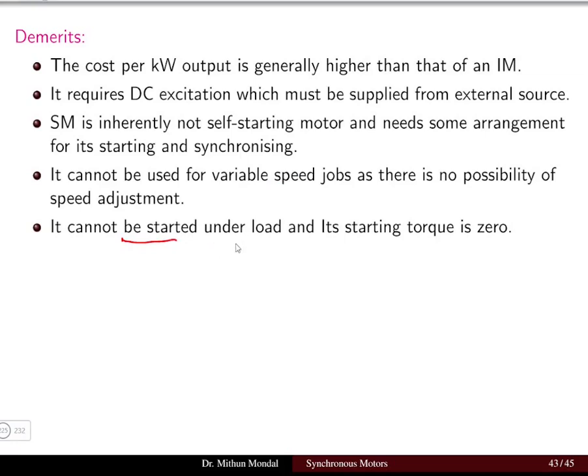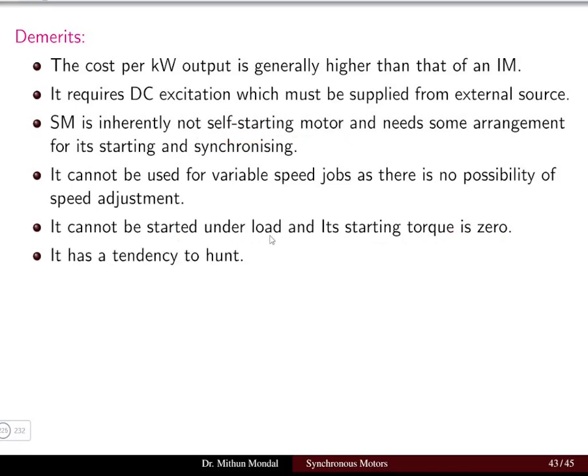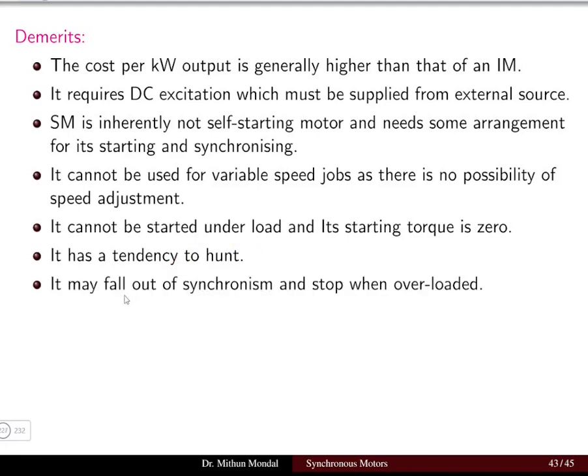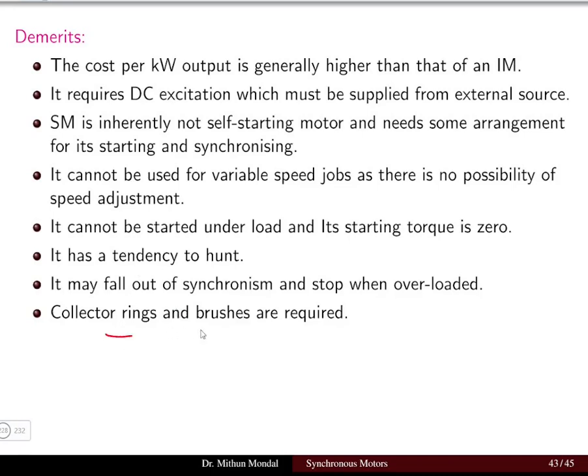The fifth demerit is that it cannot be started under load and the starting torque is zero. The sixth demerit is its tendency to hunt — the rotor may oscillate at a speed slightly less than or more than synchronous speed. The seventh demerit is that it may fall out of synchronism and stop when overloaded.